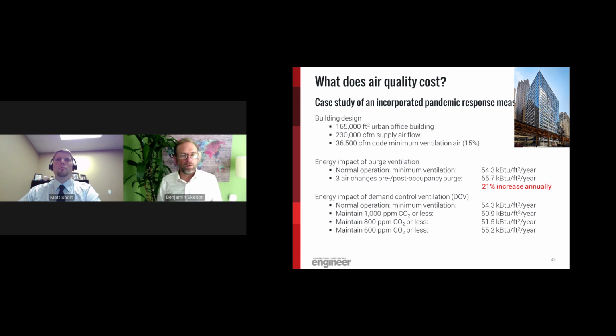And then we looked at a more recent wellness standard, the WELL Building Standard, which has a threshold around 600 parts per million. And you can see that takes us just above the code ventilation levels. So all of these have a minor impact compared to the purge ventilation. So it really comes down to how you want to operate your building and maintain it.